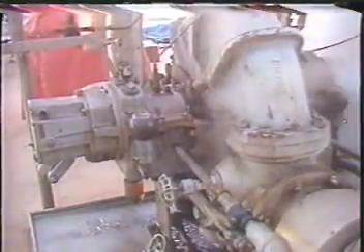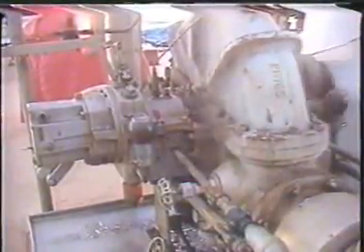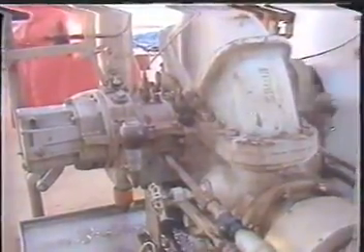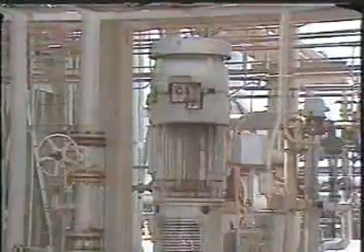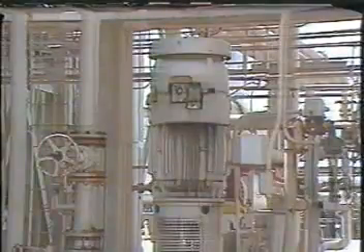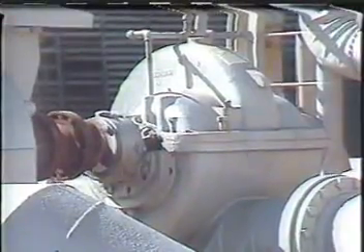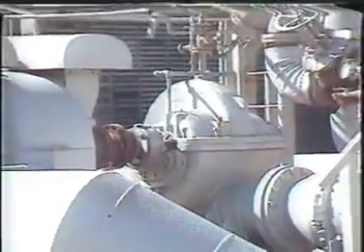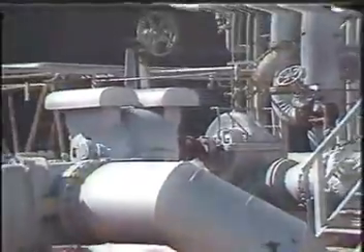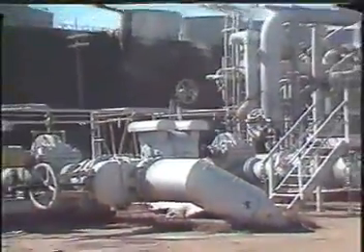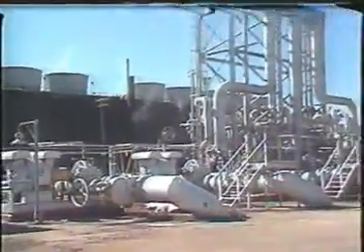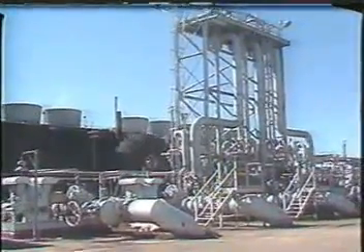The pumps you've seen so far have been horizontally mounted. The axis of rotation is parallel to the ground. Centrifugal pumps may also be mounted vertically, so their axis is perpendicular to the ground. If a pump's capacity is great enough to satisfactorily transport a specific liquid at a reasonable pressure, the pump may be operated independently. In many cases, however, multiple pumps may be required.